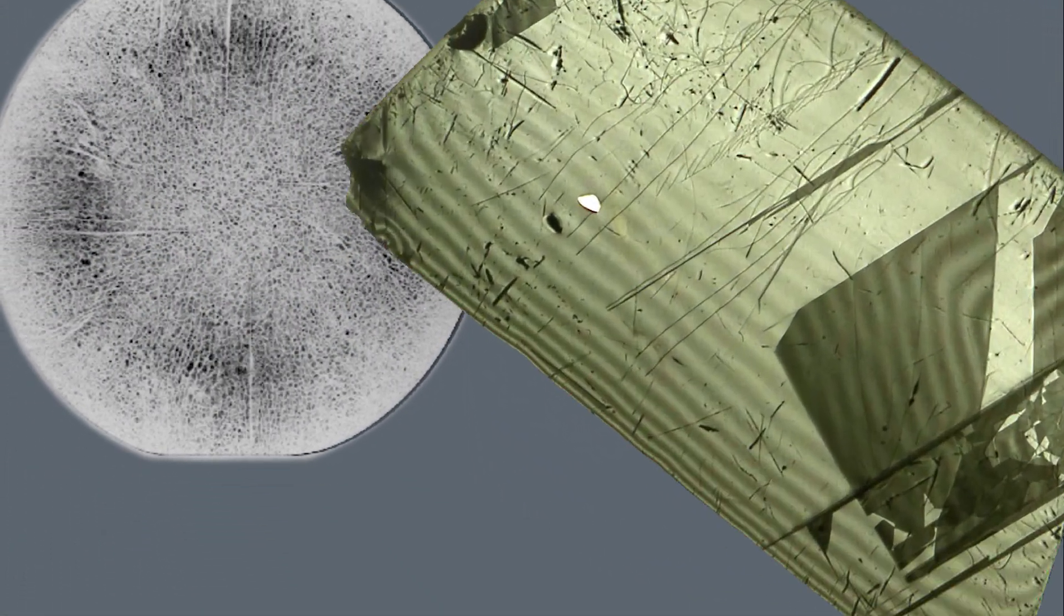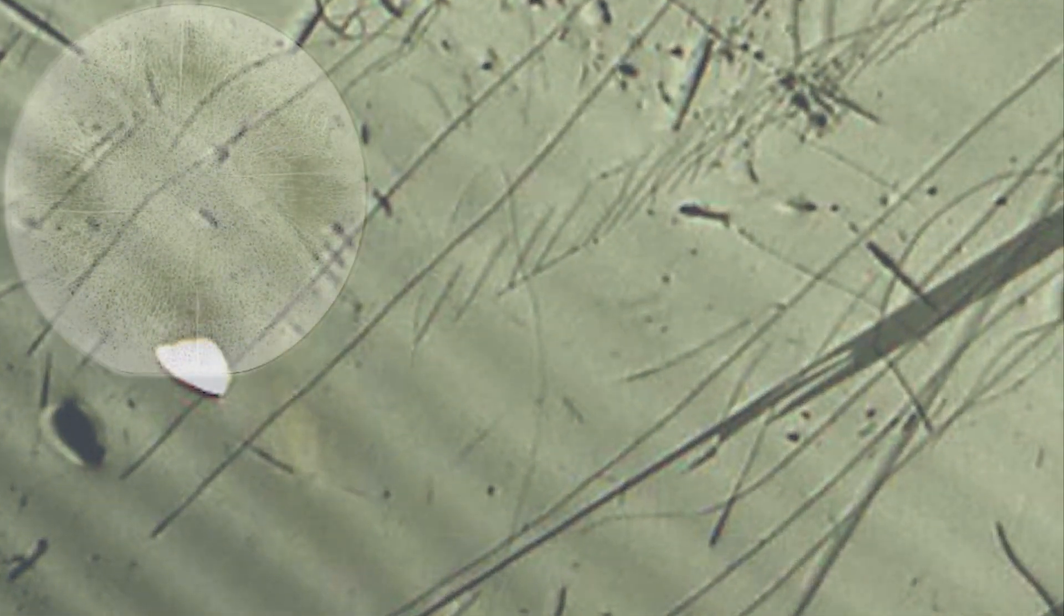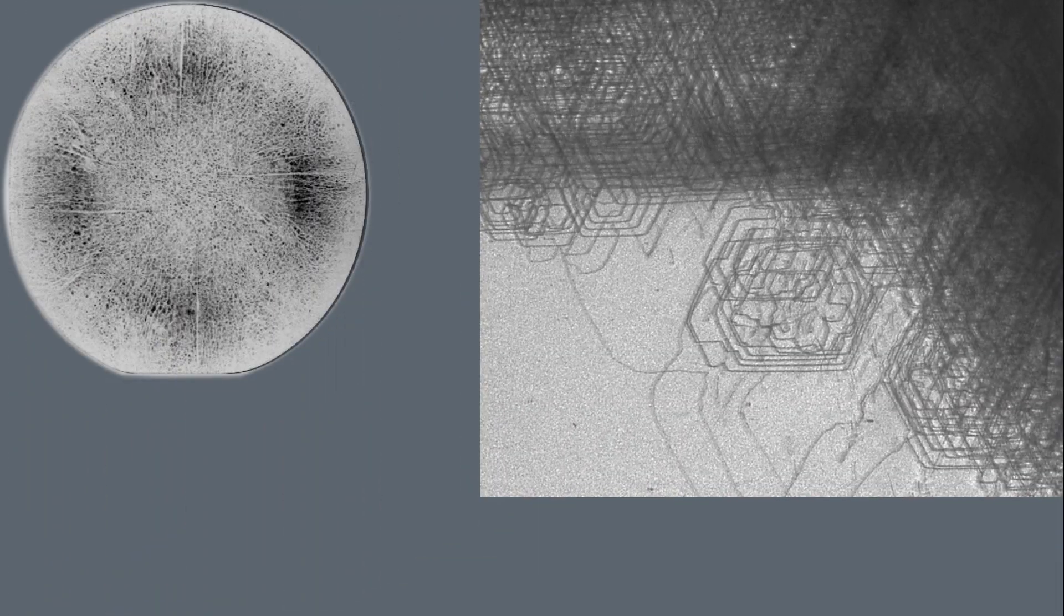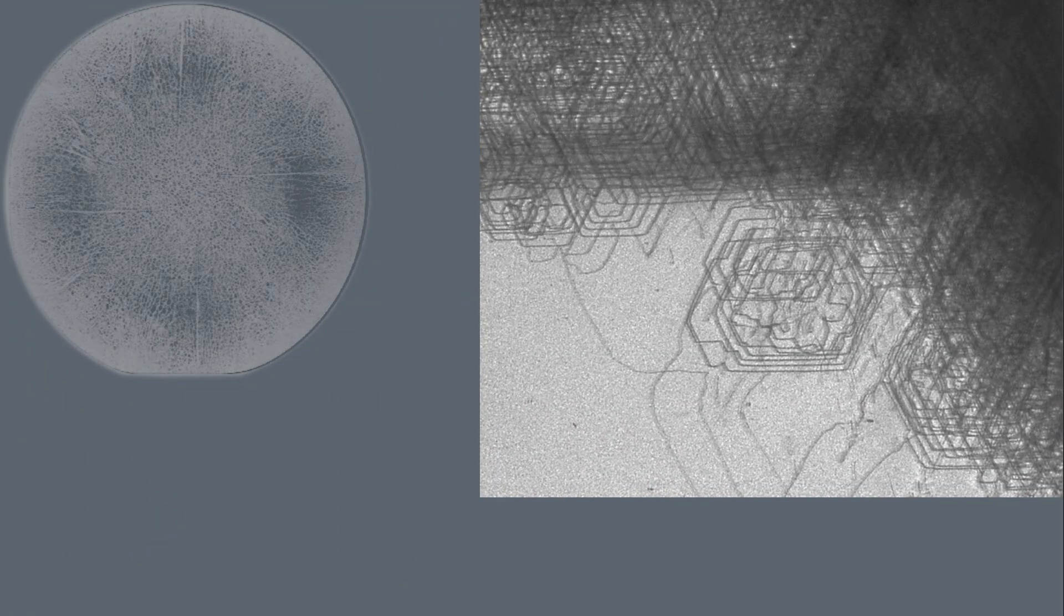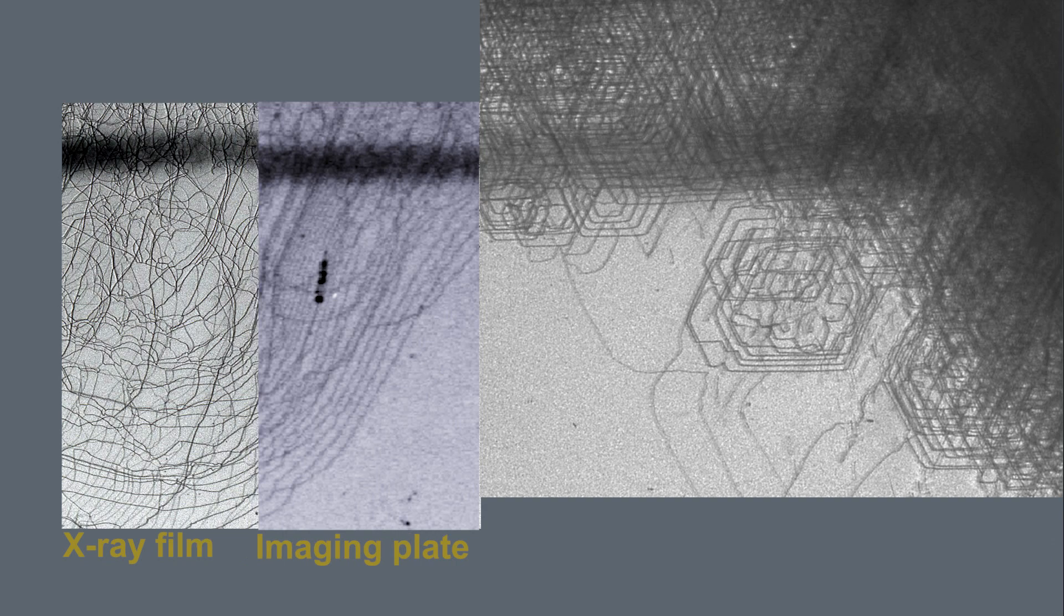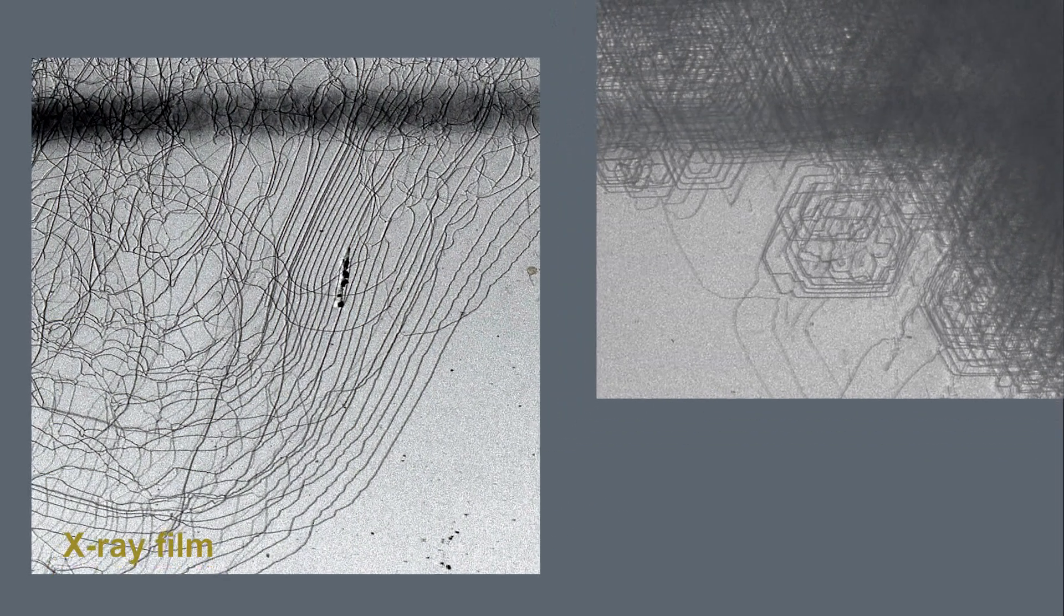A typical application of XRT is to image lattice defects in a wafer. Defects change how much intensity reaches the detector. Large defect density decreases the overall signal intensity. Localized defects on a scale resolvable by the detector show local intensity drop or increase.